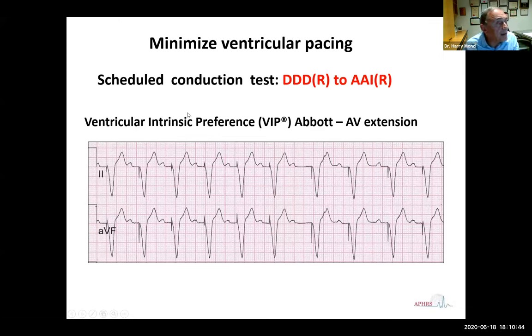Let's have a look at one which wasn't successful. This is the ventricular intrinsic preference by Abbott. You can see the pacemaker is pacing with a ventricular ASVP delay of 280 milliseconds. The scheduled conduction test extends it out to 440 milliseconds, and there is still no intrinsic QRS. So this is regarded as a failure of a scheduled conduction test, and as a result it just remains atrial sensing, ventricular pacing, like it was before. So throughout these Holter monitors, you see these extensions of the AV delay, and you wonder what's going on. These are scheduled conduction tests.